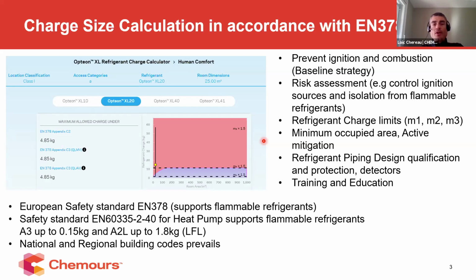Again, I'm talking about these safety standards because when we talk about refrigerants, there are different types of flammability behavior and classification of these refrigerants, be it an A2L, like the HFO blends we are developing, but also now, as we see more and more, at least discussion about the use of flammables like the propane A3 refrigerant. There is still today a very strong limitation on the charge size, which is 150 grams for such flammable products. And because of that, there are clearly some restrictions and limitations on where propane can be used in terms of charge size, and therefore the heating capacity that can be achieved for such heat pumps.